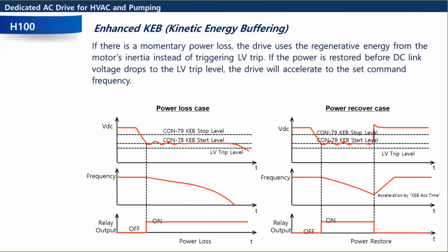One of the more advanced features we have, you may or may not use, is our KEB, which we've enhanced on the H100. So it's kinetic energy buffering. What it's doing is if you ever have a power loss, the motor will typically still be spinning as long as there's a decent amount of inertia in that motor or on that load. So when the motor's freewheeling, it's acting as a generator. So it's regenerating. We'll take that regenerative energy from the inertia and use that to keep the power up in the drive, keep the DC power up, and that'll prevent a low voltage trip. Okay, so there's one less trip you've got to worry about. Use that energy to keep the drive powered up.